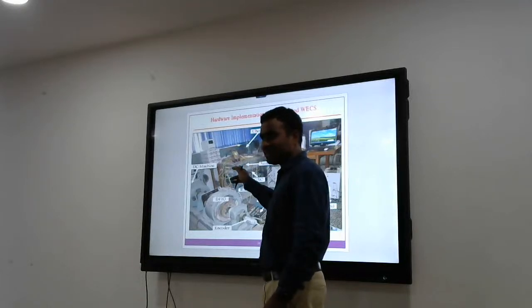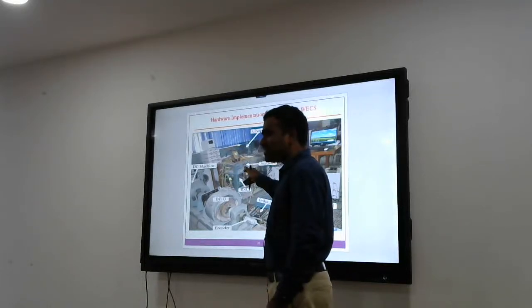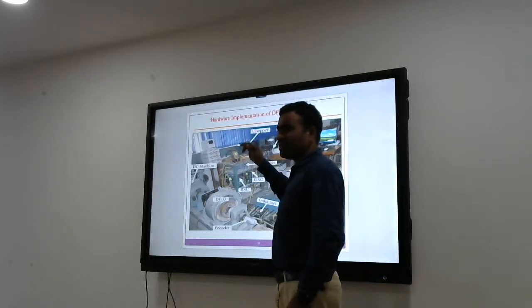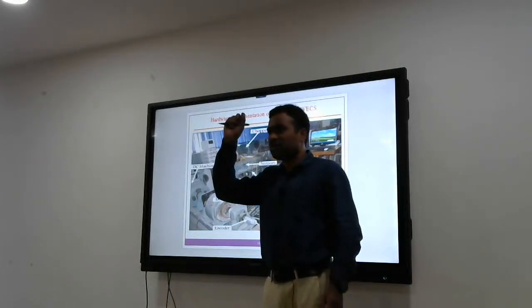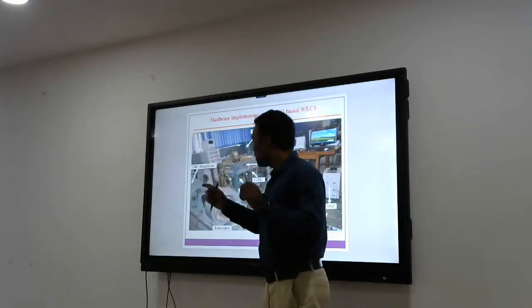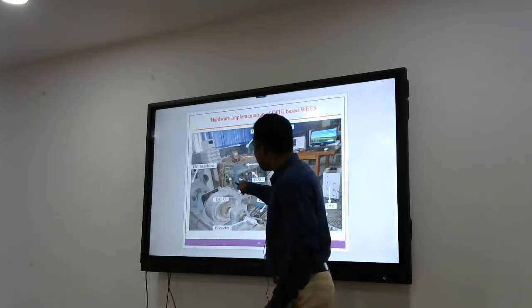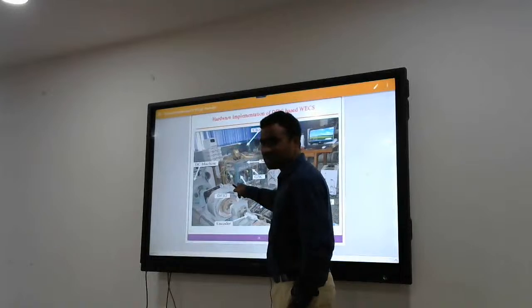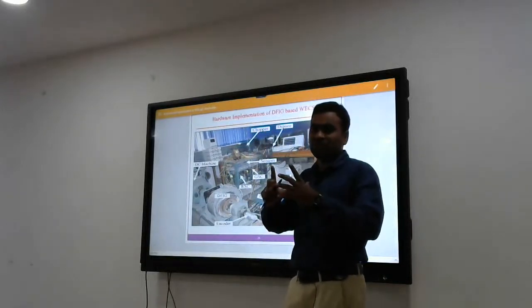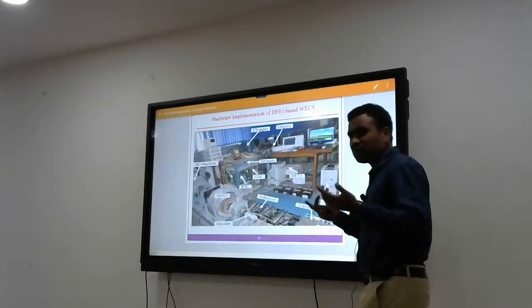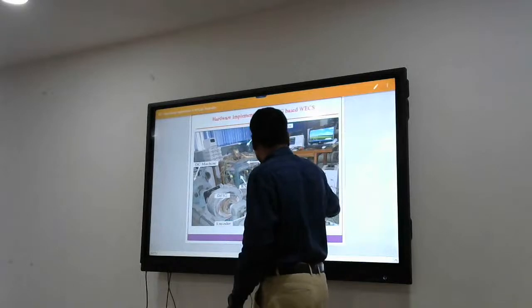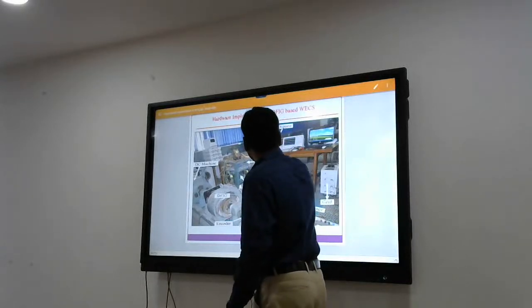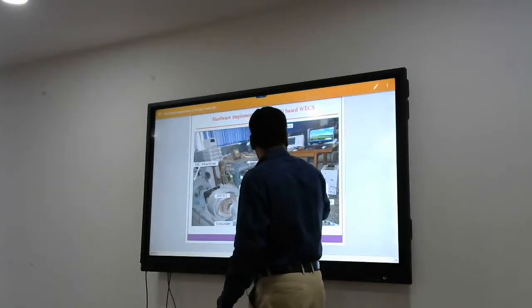You need sensors. Here we have sensed everything, and after sensing, it will give it to the display and do the comparison. Here we will tell I need 415. Then it will sense, oh, 400 volts is there. Now increase my modulation. It will give some pulses, and these pulses will increase the modulation. This converter will operate at higher modulation, and you will get some different voltage. Like that. Here, this is what was left.